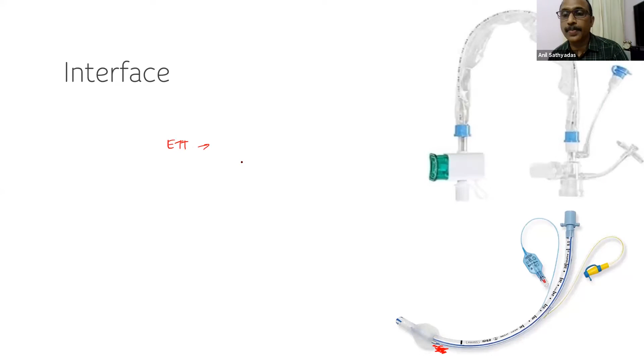So after putting in a tube with suction aid, you should keep a closed suction. This is the closed suction device where you attach this end to the endotracheal tube, and the ventilator tubing should come here. So this would remain like that. And whenever you want to give suction, you attach the suction tube here and just press this switch and introduce the tube, and then activate the suction by pressing the green switch.